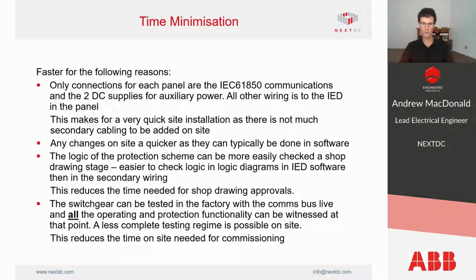The switchgear can also be tested in the factory with the comms bus live, and all of the operating and protection functionality can be witnessed at that point. It means that you potentially can reduce the amount of testing needed on site, which in our case reduces the site installation time.